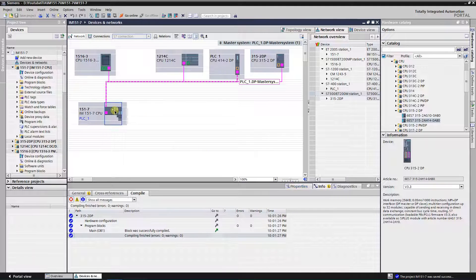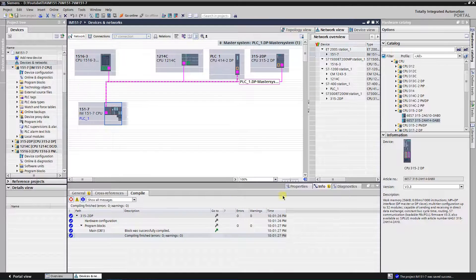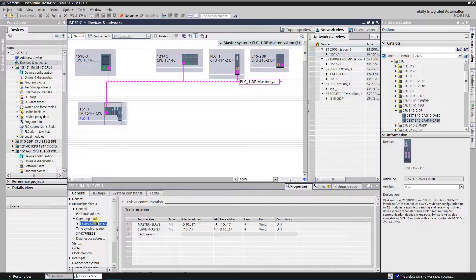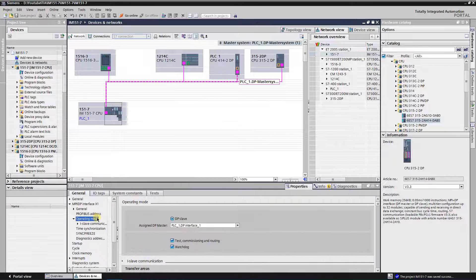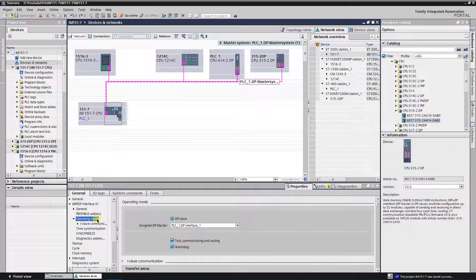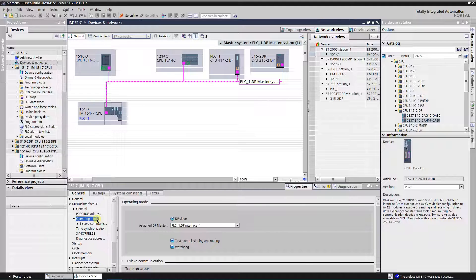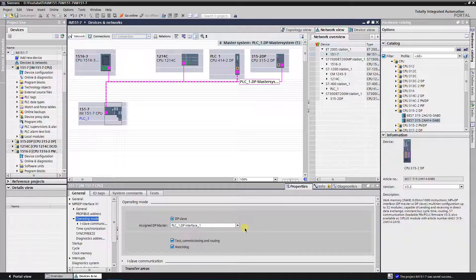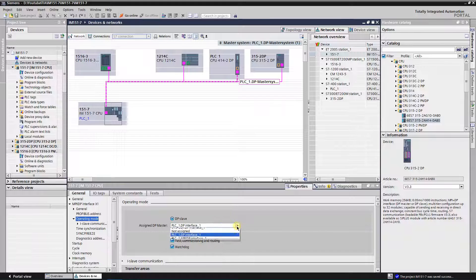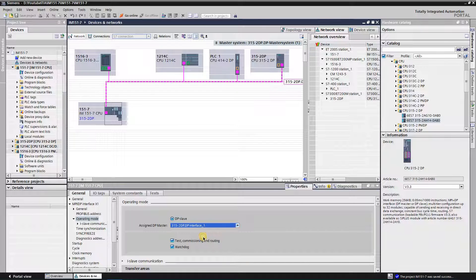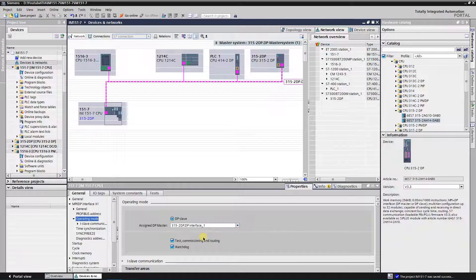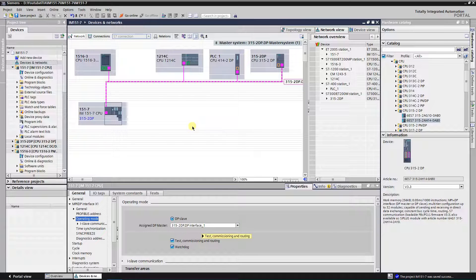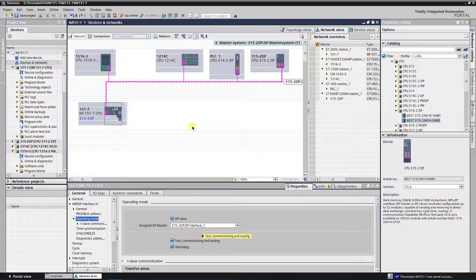Select IM1517 CPU. Switch to the properties, general tab, MPIDP interface, operating mode. Currently, PLC1, which is S7400 is assigned as master for IM1517 CPU. Expand drop down list, and select 315-2DP master interface as DP master. IM1517 CPU became an i-slave of 315-2DP master system.